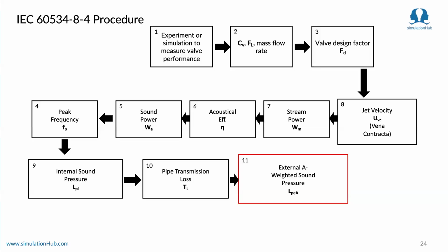And in the IEC standard itself, they introduced a term which is acoustical efficiency, eta. This also varies depending on the Mach number of the flow. So again, there are many parameters that depend on the design and on the internal flow, and there's a lot of dependencies that you must know a priori to getting these hydrodynamic noise values.